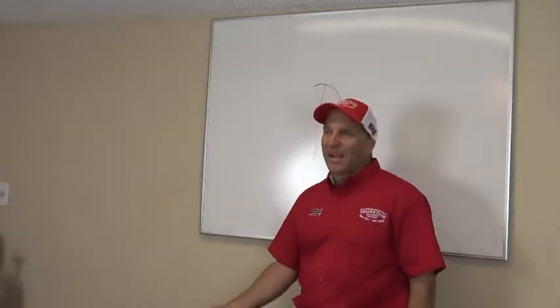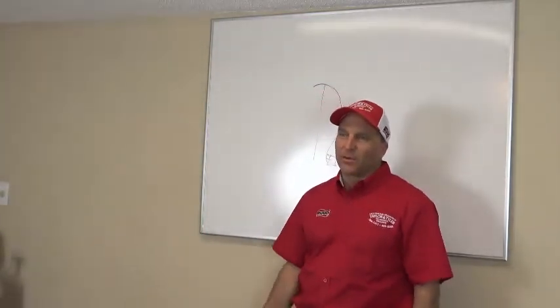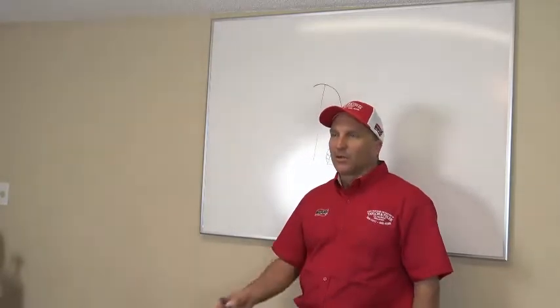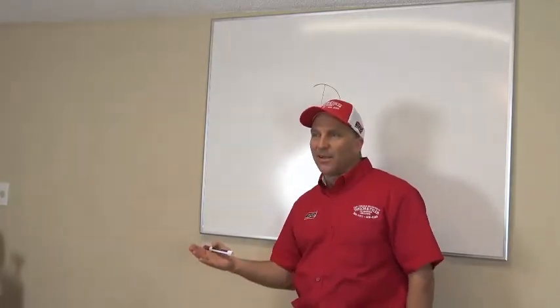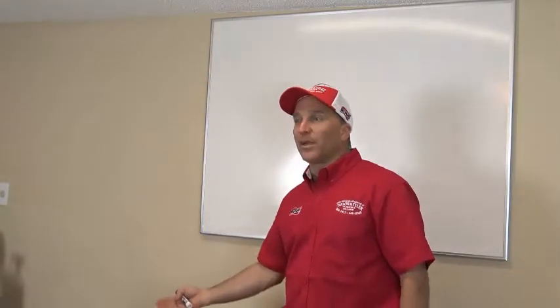Why is your subcooling 18? Well, I just let a little bit of refrigerant out, right? If I let a little bit of refrigerant out, my subcooling's 18, and my superheat's going to stay the same, right? So if I let refrigerant out, bring it down to 12, isn't my superheat going to stay the same?